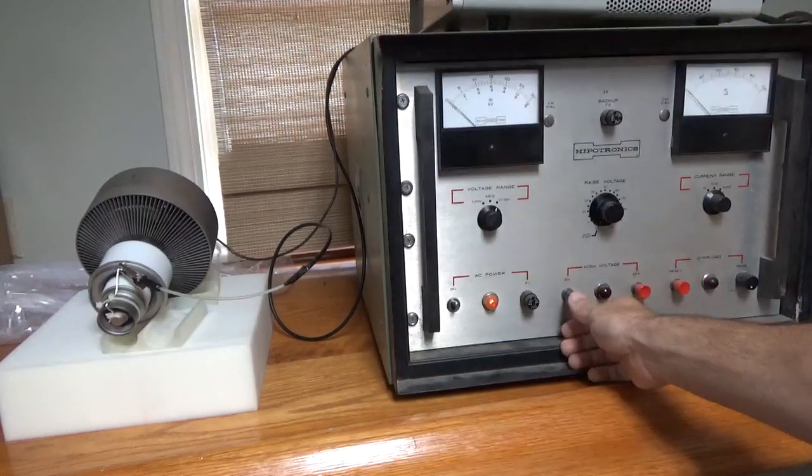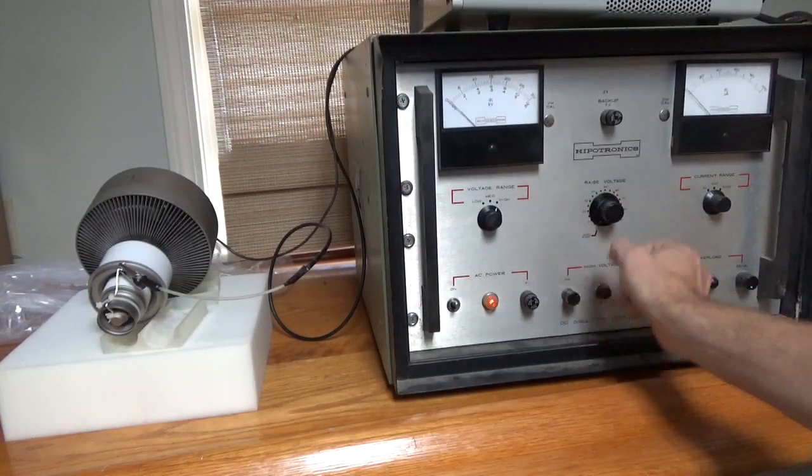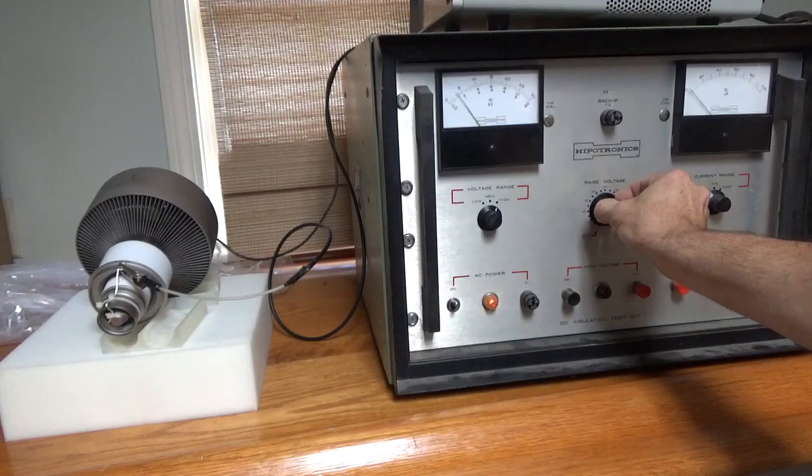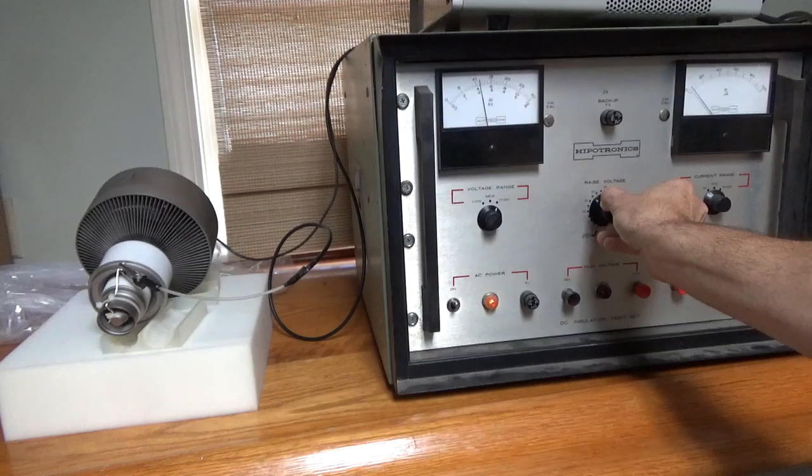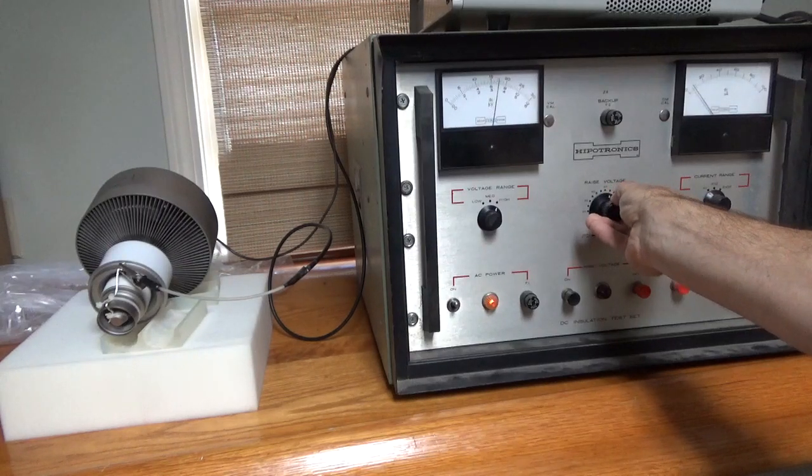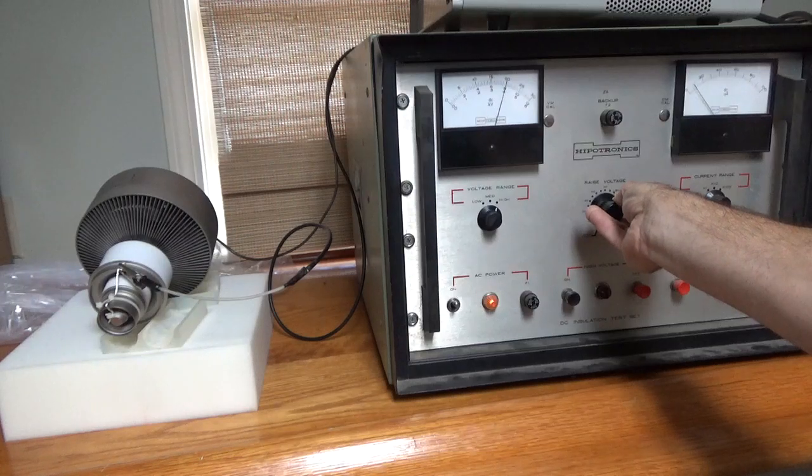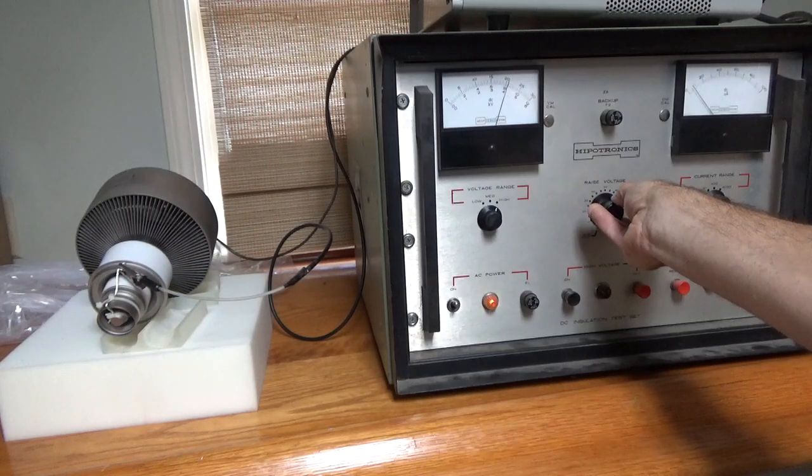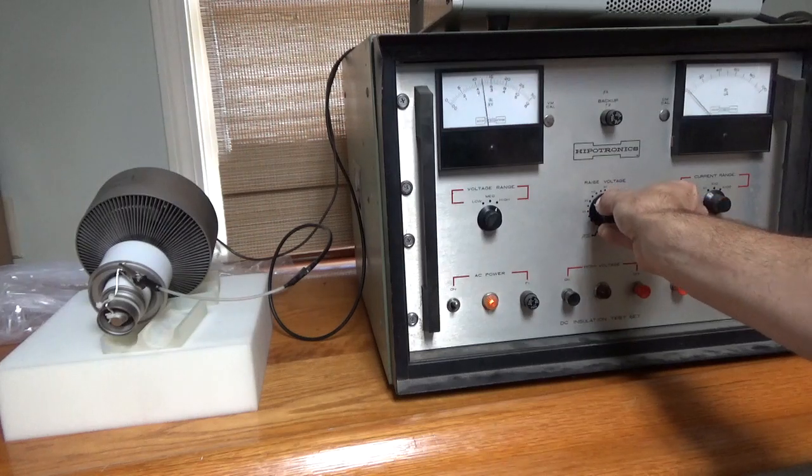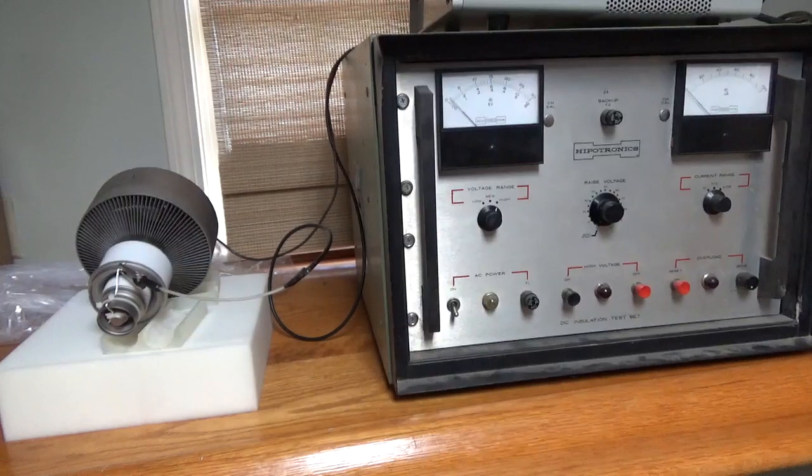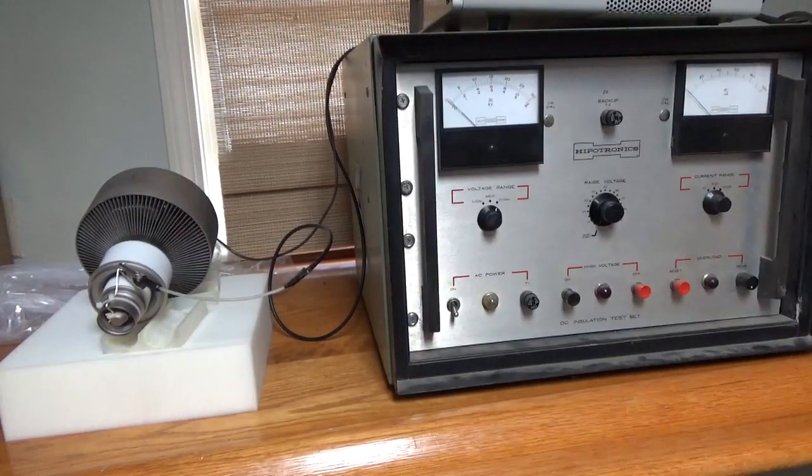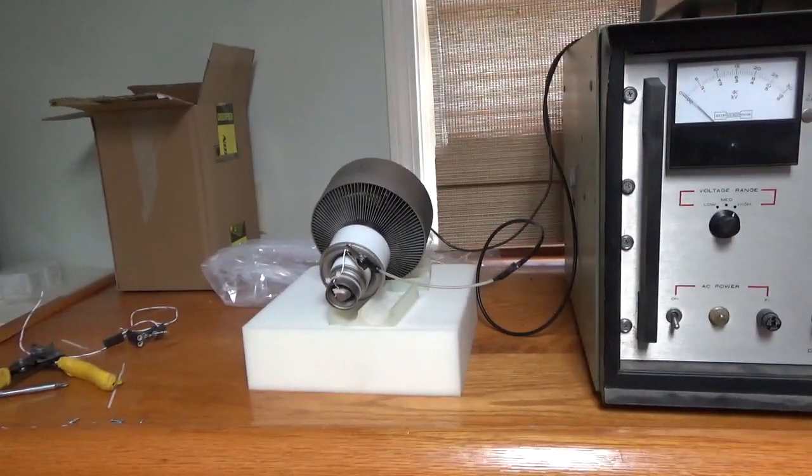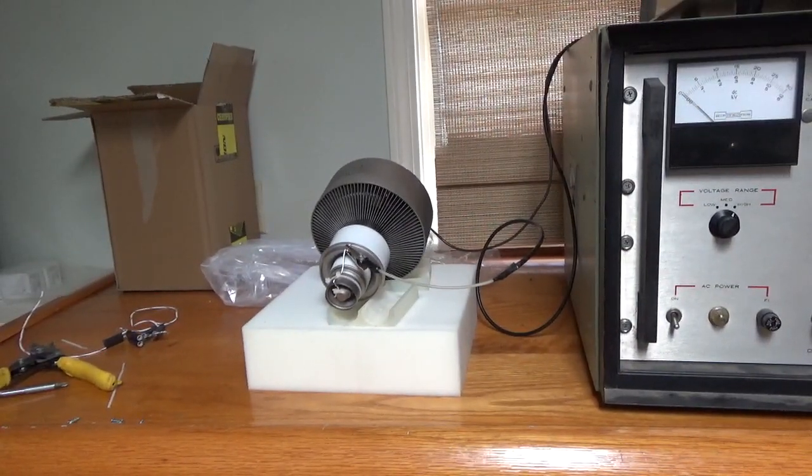Okay, polarity reversed. Put it away then. Okay, looks good. Okay, now I will reconfigure the shorting wire. I will short the anode to the grid and then high pot between the grid and the filament. See you soon.